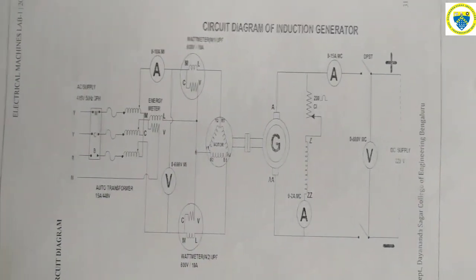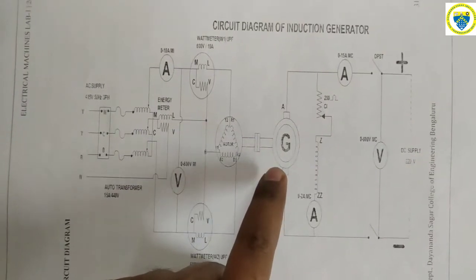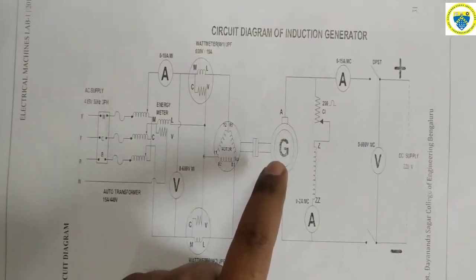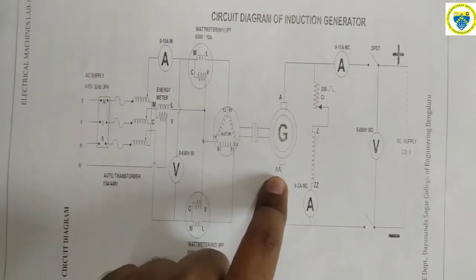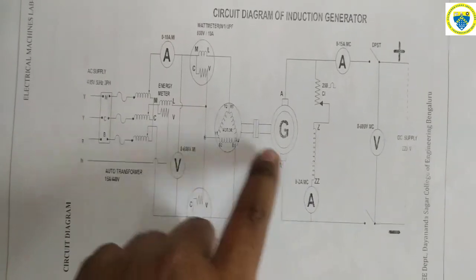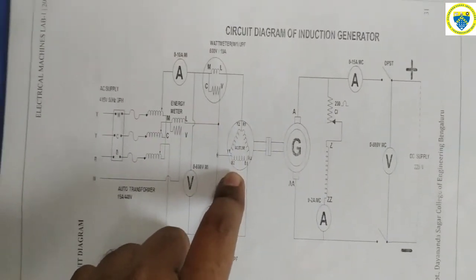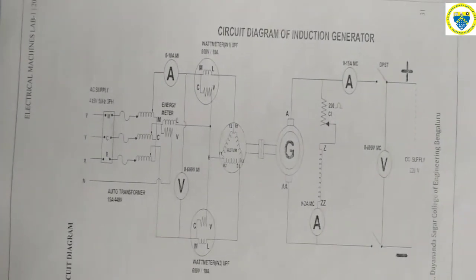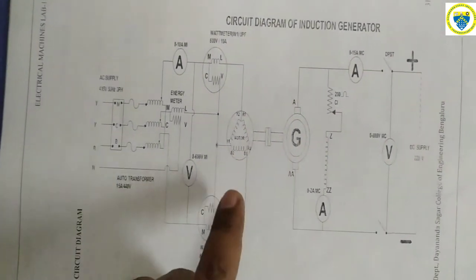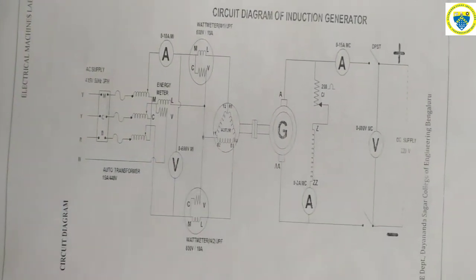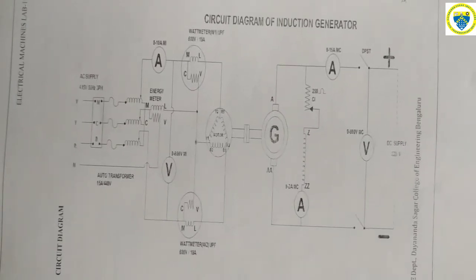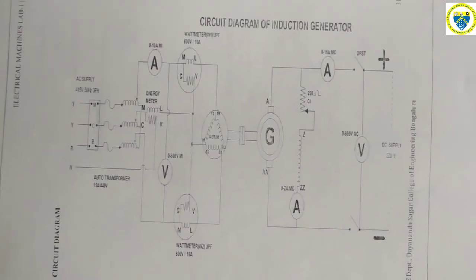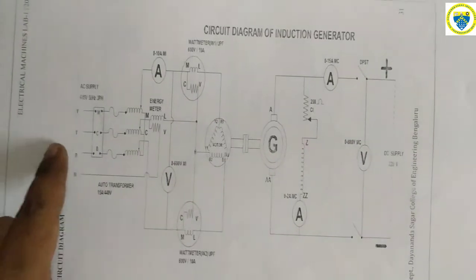Then we will make this generator work as a motor, and at that time this DC machine, which is acting as a motor, starts driving this induction motor at more than its synchronous speed. At that time the induction motor starts rotating above its synchronous speed, and it will start acting as a generator, giving supply back to the mains.